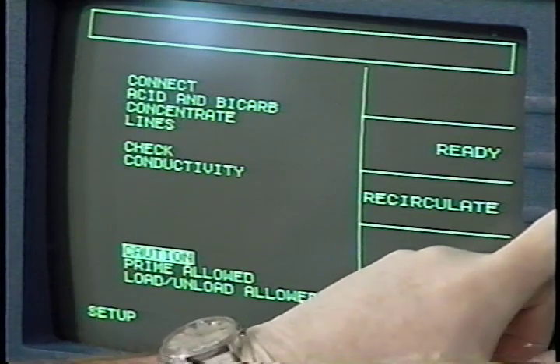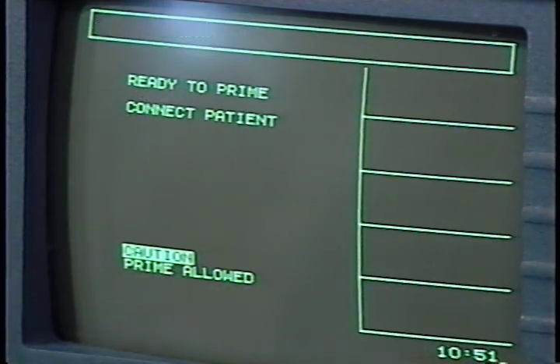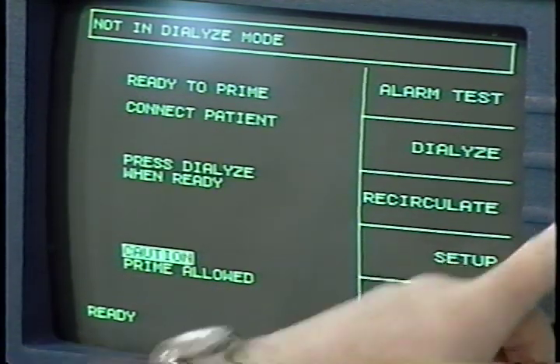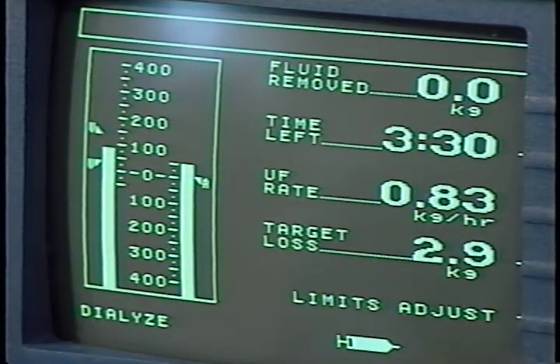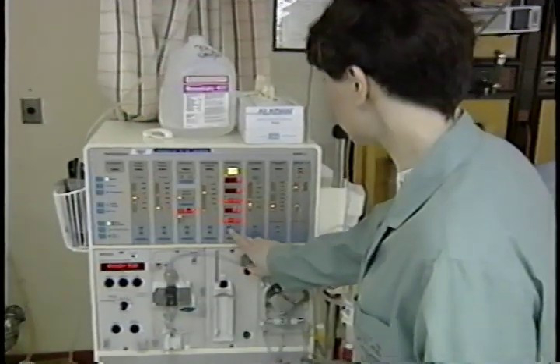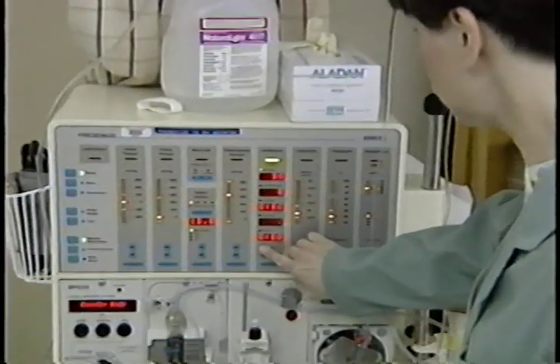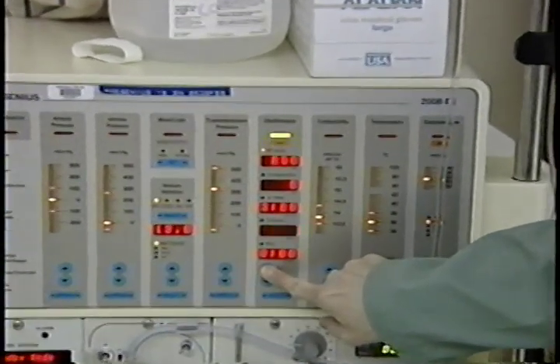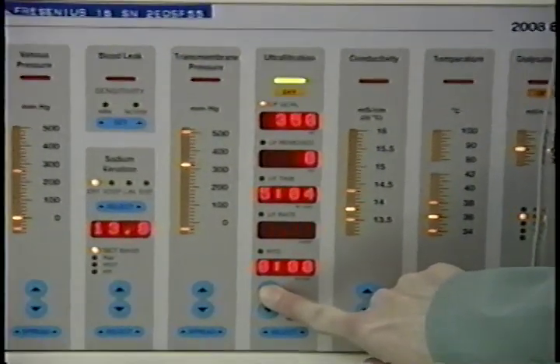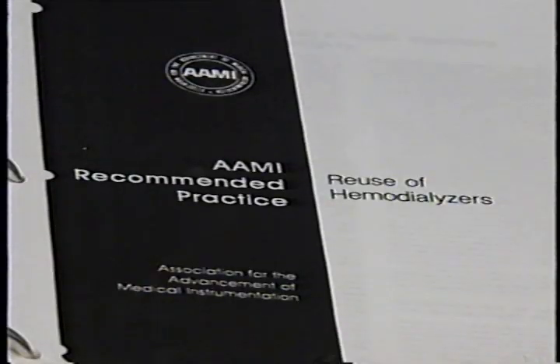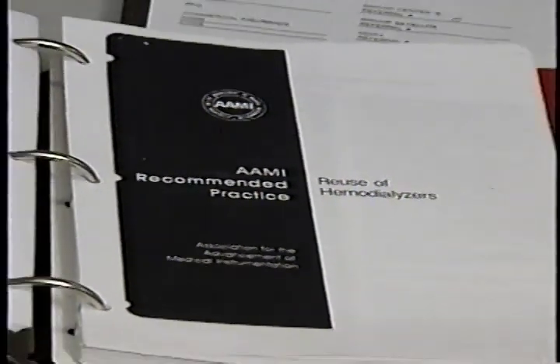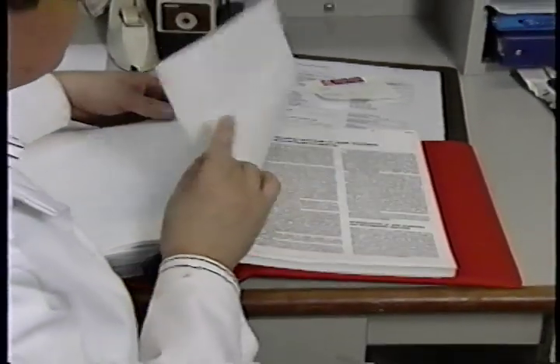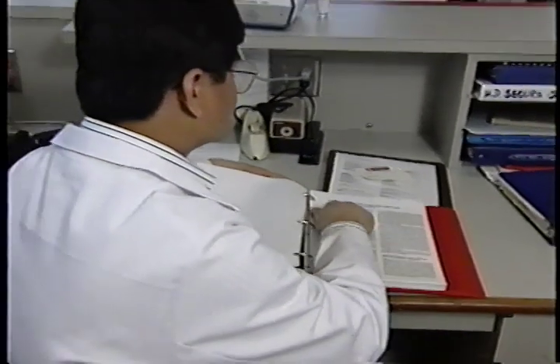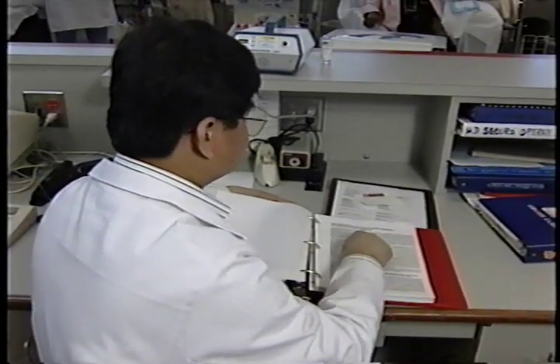Blood flow and dialysate flow must be set according to the physician's prescription to achieve the expected dialyzer clearances. Some machines have a preset dialysate flow rate that cannot be adjusted. Your facility's quality assurance must make certain that the prescribed dialyzers are being used, that the blood and dialysate flows are accurate, and that reprocessing is performed according to the AAMI recommended practices, federal regulations, and your facility's established procedures.